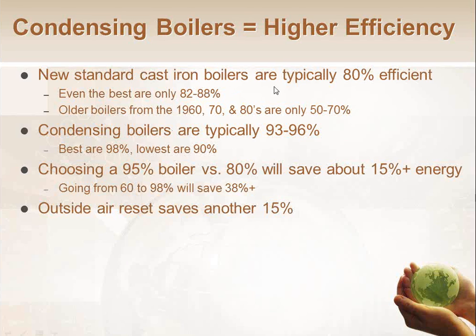But the point is it's going to derate itself as the age goes on. Condensing boilers, on the other hand, are going to be 90% and better. And a lot of them seem to be in that 93, 94% range. That's a pretty common point for most manufacturers. So 93, 94, 95, 96%. So if I go from an 80% to a 95% boiler, I'm going to save basically 15, 16% energy.